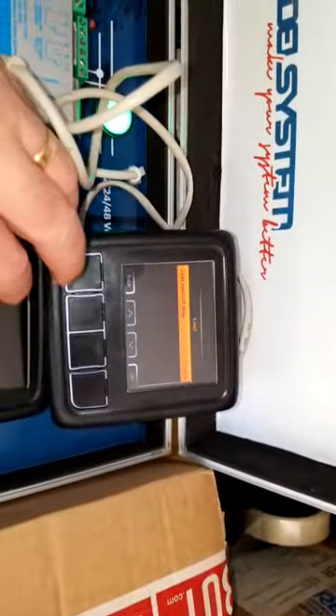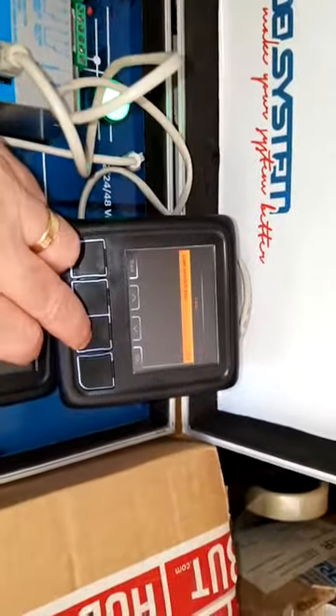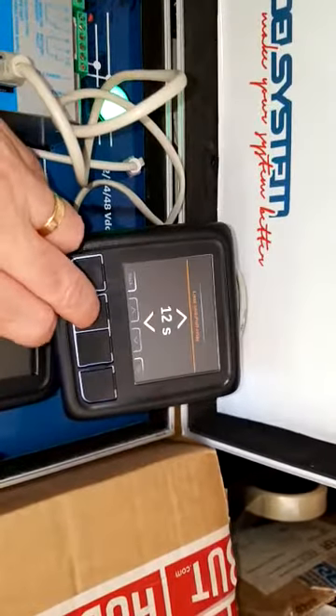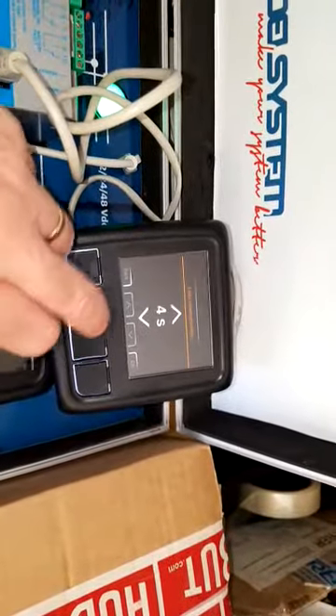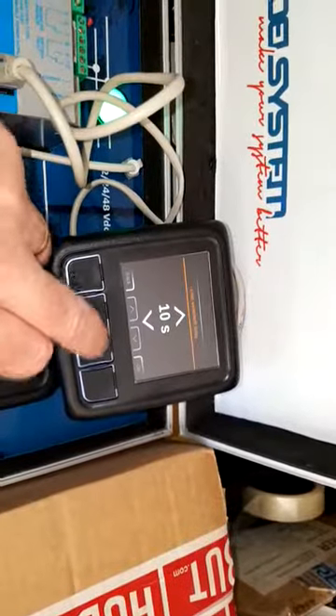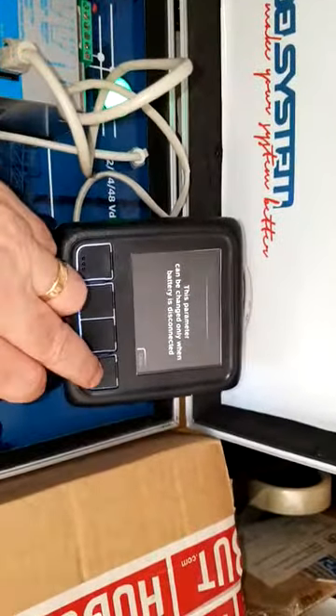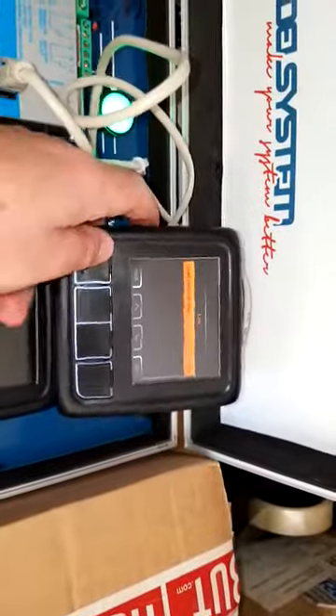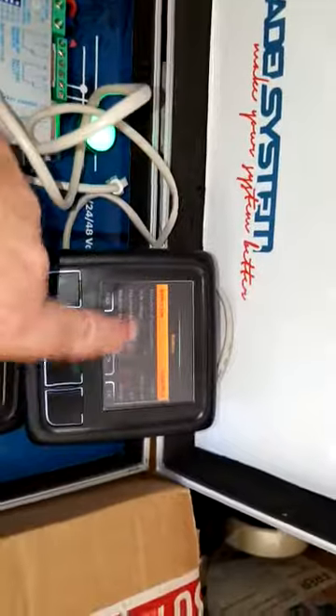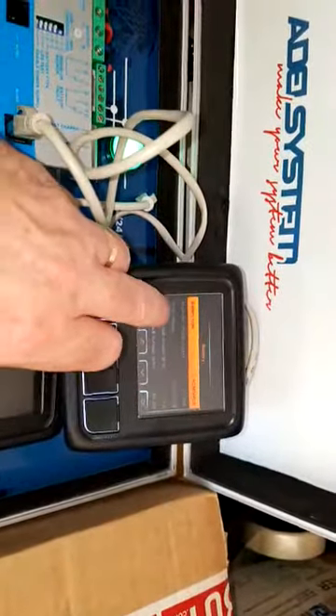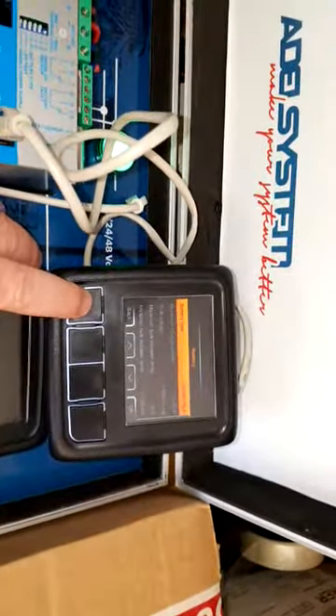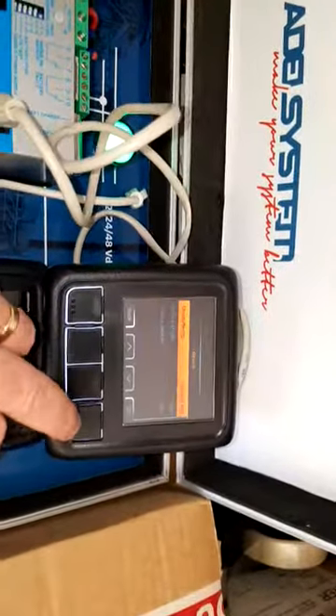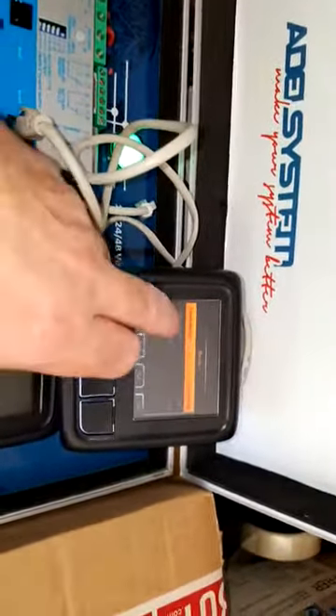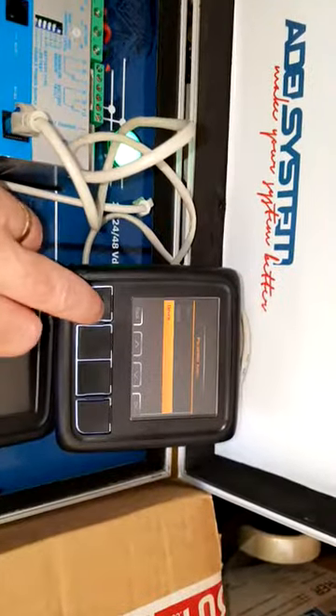So you get load on the battery, so you can switch the load off time after a number of seconds. You can press OK on that, and you can reduce that to whatever you like, but its default is 10 seconds. I can't change that parameter when the battery is connected, because there's a battery connected. The battery type, again, you can change all the characteristics of the battery type, and particularly your bulk charge voltage, so you may get the right charge voltage for your type of battery. And then the device itself: time buffering, backup enabled, and then factory restore settings.